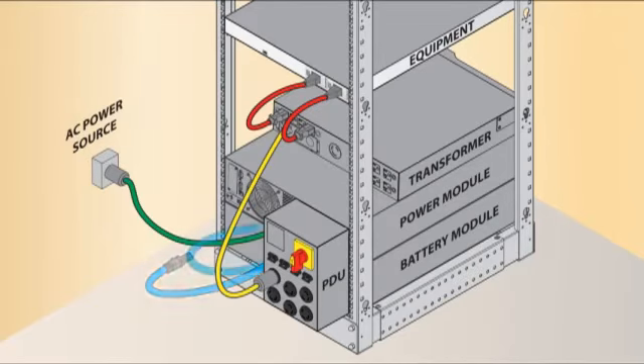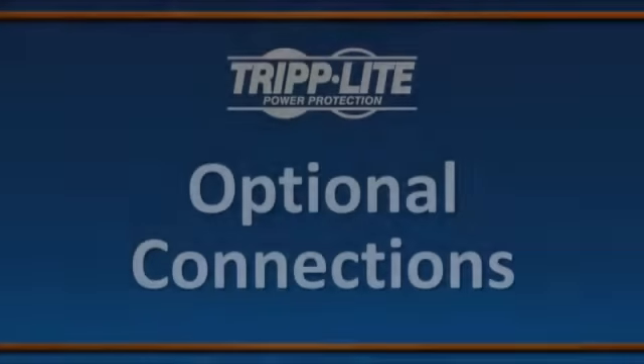Finally, connect the battery module to the power module. Small sparks may result during this connection. This is normal. Do not connect or disconnect battery modules when the UPS is running on battery power.